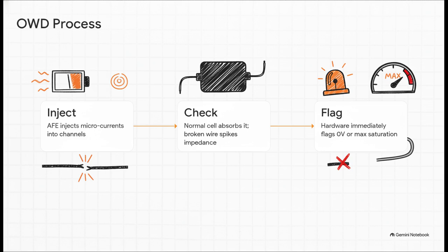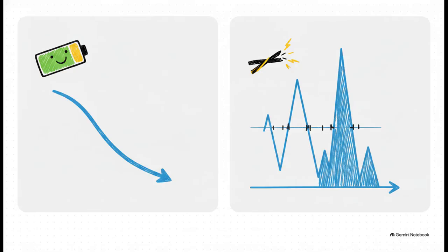And then we have our software stepping in as the second line of defense. It constantly analyzes the dynamic voltage rate of change, or dV/dt. Normally, a battery drains or charges in a super smooth, incredibly slow, flat curve. But a broken wire produces a violent, sudden cliff drop or a massive spike. By continuously monitoring this rate of change, the software can instantly filter out random noise and accurately declare a true physical break.